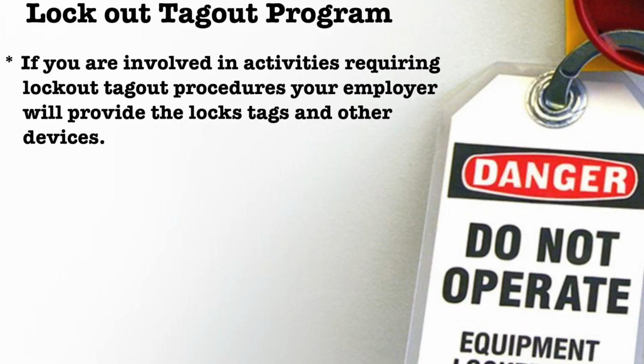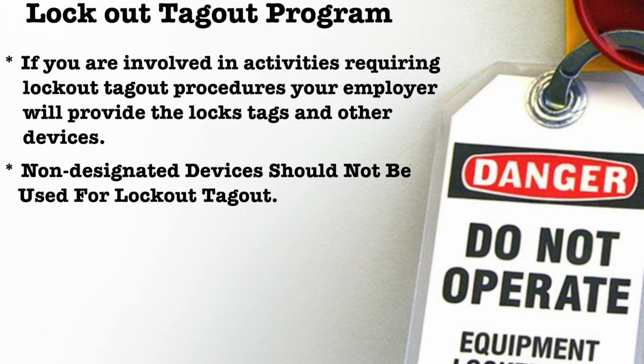If you are involved in an activity requiring lockout tagout procedures, your employer will provide the locks, tags and other devices you will need. These must be identified as lockout tagout devices. They can only be used for this function and may not be shared with any other workers. You should also never use non-designated devices for lockout tagout.